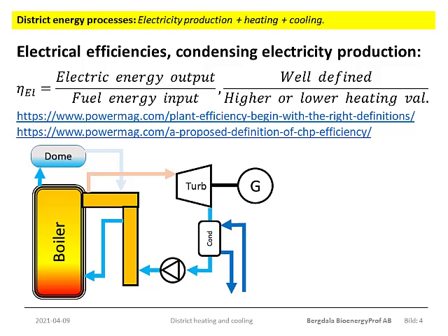So in most cases the pressure is only about 150 to 160 bar, and the temperature is only about or below 600 degrees. And there may be other limitations. If the combustion gases contain corrosive components like chlorine or sulfur compounds or vanadium or such, then the corrosion from the outside of the superheater tubes will be part of the limits. So we have the steam corrosion from the inside and the eventual corrosion of flue gas components from the outside.